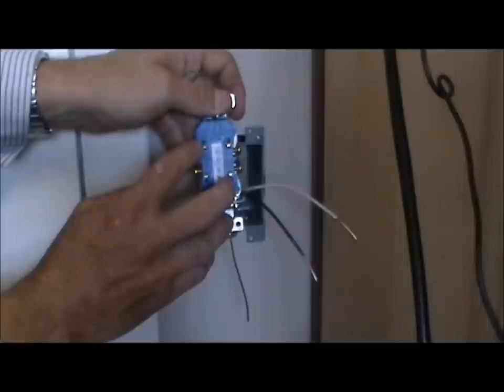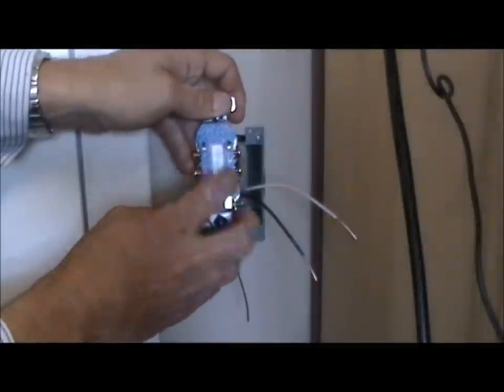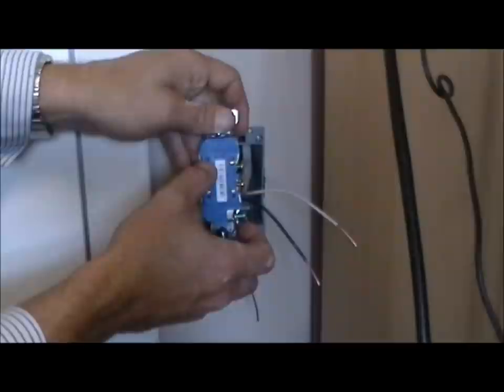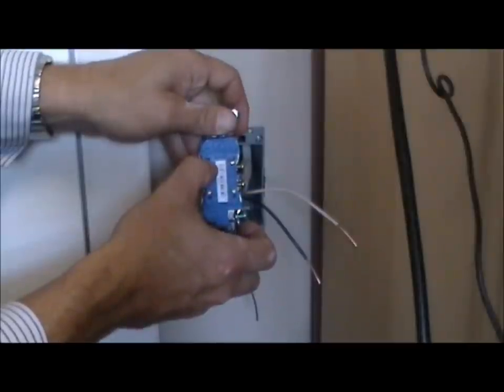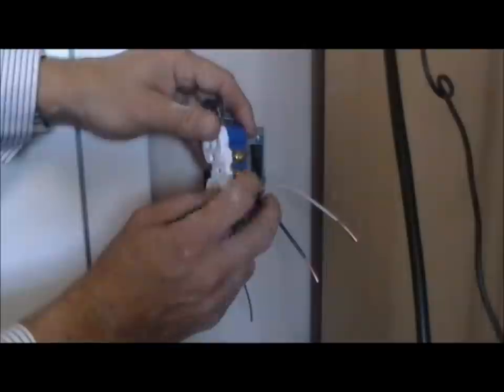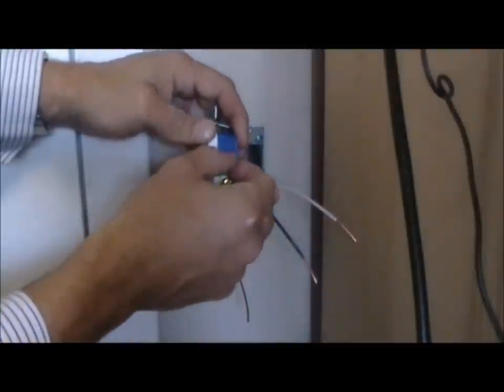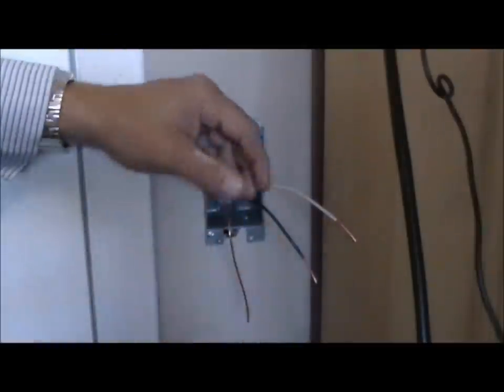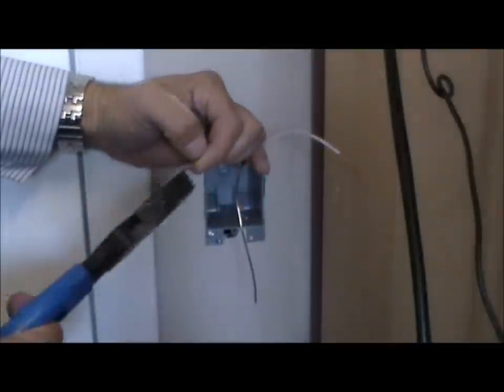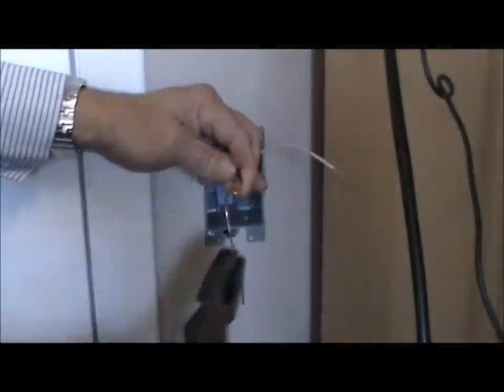Now, modern outlets have quick connects in the back. As a company, we do not use them. They have a tendency to get loose, and they trip our fault breakers. So what we do is we make the wires so they go around the screws, which is a much better and tighter connection. To do that, you want to put a half twist here on your wire.